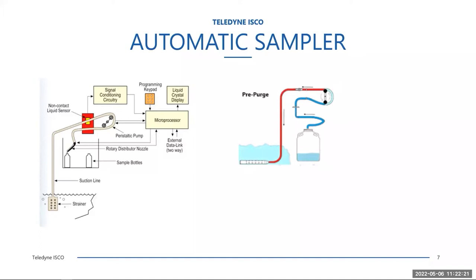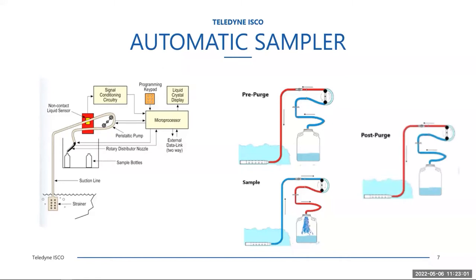The whole goal when that sample is collected is that the sample delivered to the bottle represents what's in the flow stream at the time it's collected. You do not want that sample to represent what's been sitting in the line for the last 15 or 30 minutes. Once it has purged the line, it will run forward and pull the sample up, delivering the programmed volume into that bottle. Once the sampler has delivered the programmed amount, it will run the pump in reverse again to purge and clear the line of all residual fluid, so the line is free and clear and able to deliver the next sample without any cross-contamination from previous samples.